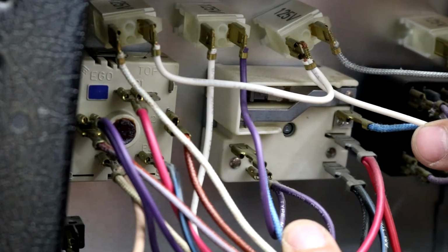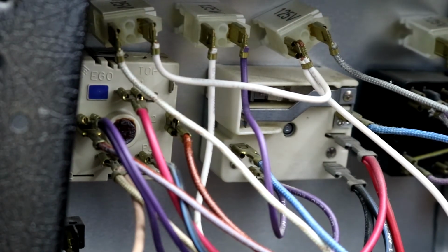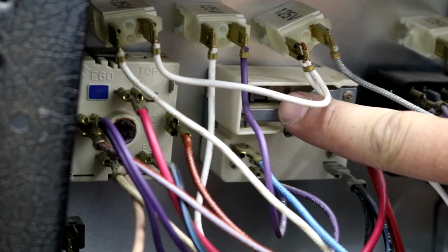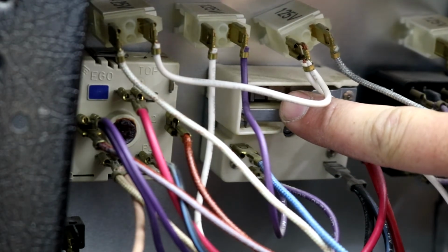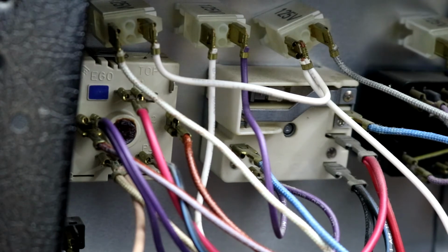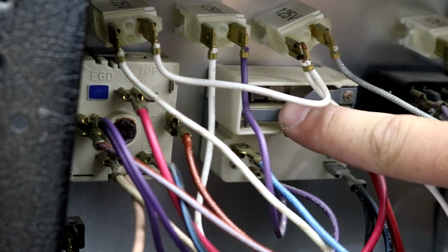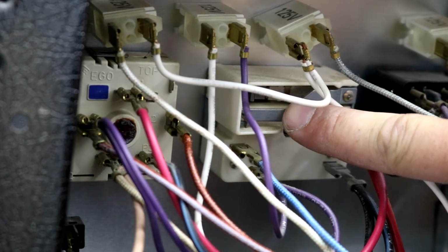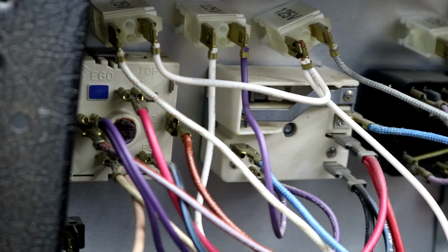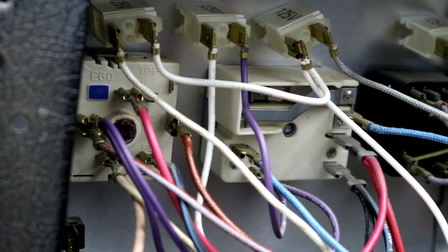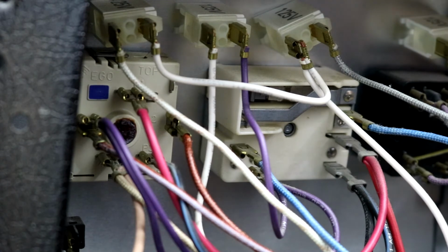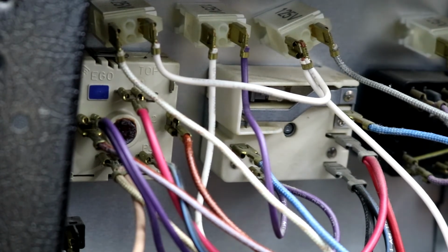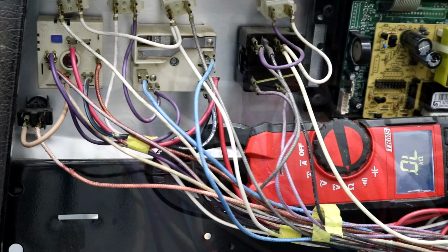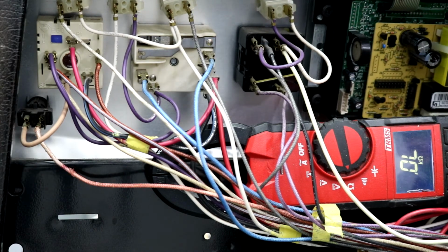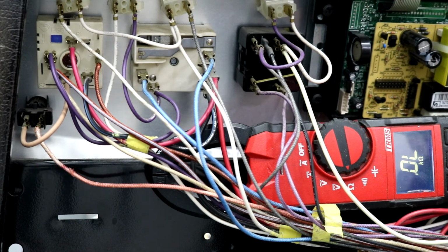Now how this thing works is when you have this set on a low temperature, it only takes a little bit of current to kick the bimetal off inside, and as you turn this up to a higher setting, there's more pressure on that contact, so it takes a lot more current and a lot more heat for it to break the contact. And when you set it to high, it forces it closed, and the temperature probe limits the maximum temperature.